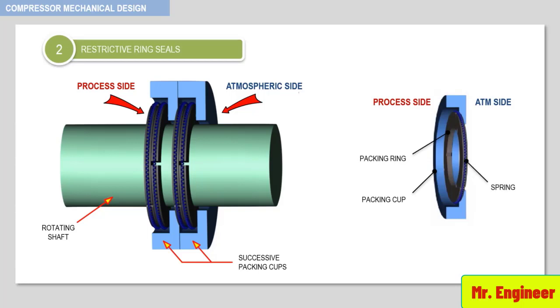Packing cups are placed on the shaft. The number depends on individual unit requirements and the process conditions. The material of construction is usually carbon. The rings are housed in a case which is mounted in a stuffing box. These rings fit closer to the shaft than the labyrinth seals, and for that, the leakage is well controlled.